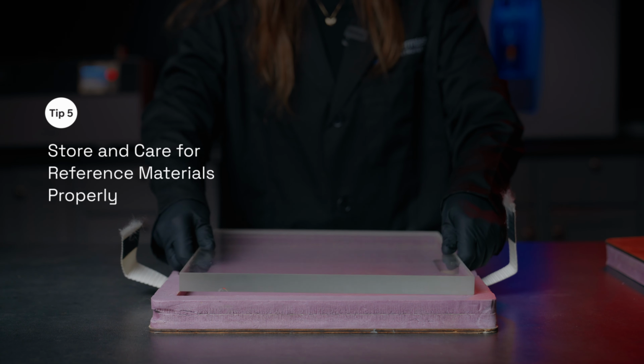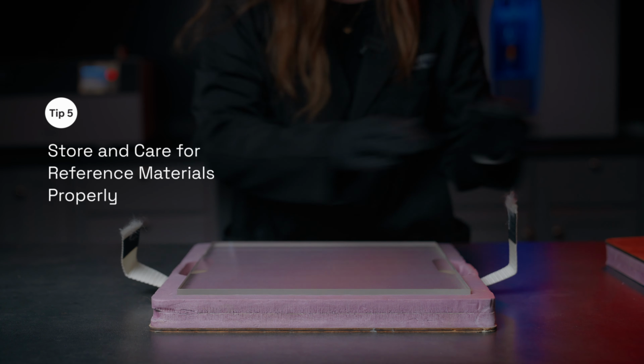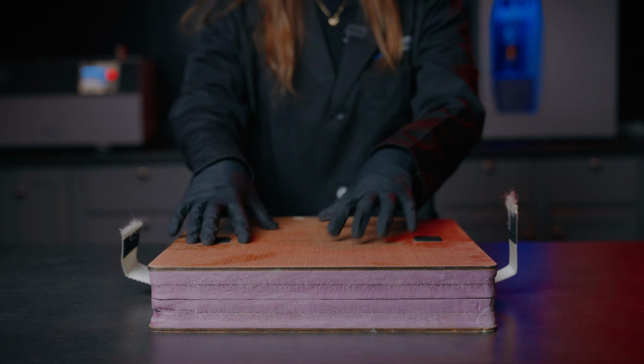Reference materials are only reliable if they're properly stored. Keep them clean, dry, and protected from contamination or extreme temperatures. Proper care ensures they remain a dependable benchmark for calibration and verification testing. Instrument calibration isn't a one-time task, it's an ongoing process. It starts with proper calibration when the unit is received and continuous regular verification to ensure that calibration remains valid. By taking a proactive approach, monitoring performance, controlling environments, handling equipment carefully, and verifying regularly, you can maintain confidence in your results, extend your instrument life, and minimize unexpected downtime.